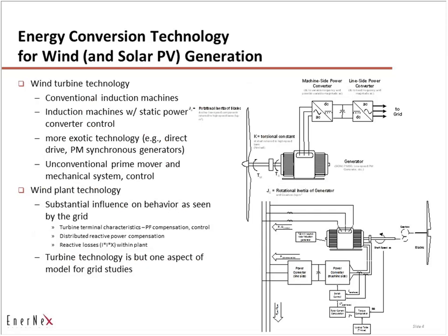The technologies themselves initially posed big challenges because there simply weren't the pieces and parts in the dynamic model libraries in either PSSE or PSLF to represent the technologies employed for renewable energy conversion. We're talking about induction machines, possibly permanent magnet synchronous generators, with a lot of control influenced by static power conversion technology — unlike the six-pulse rectifiers and HVDC building blocks that utility engineers were more familiar with.